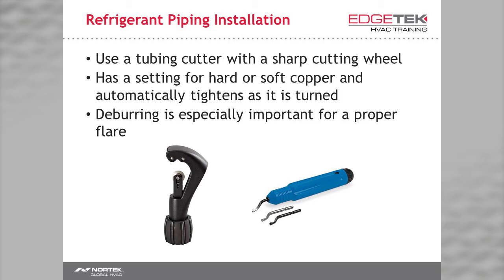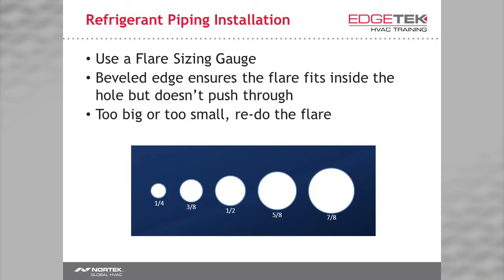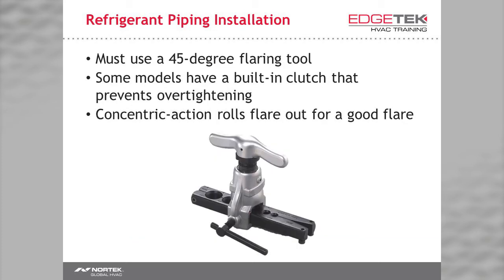A deburring tool is important so we have a nice surface on which to flare. The only foolproof method to determine if your flare is the right size is by using a flare sizing gauge. If it is too small or too large, you'll cut it and try again. You must use a 45-degree flaring tool. I like using a flaring tool with a built-in clutch. It helps to prevent over-tightening.